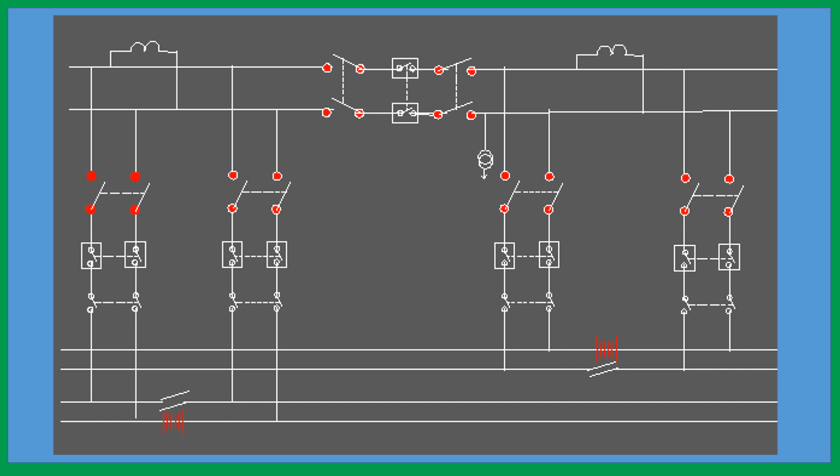Our system is main line will be 2 into 25 kV, and the siding line, yard line all will be in 25 kV. The system, what it is, simply provide an auto transformer, take the plus 25 terminal to OHE and neutral point of the auto transformer to the track, and the feeder line is not required, that will be kept opened. So I think it is clear to you all.